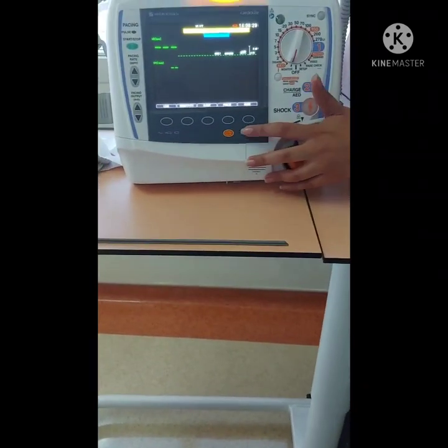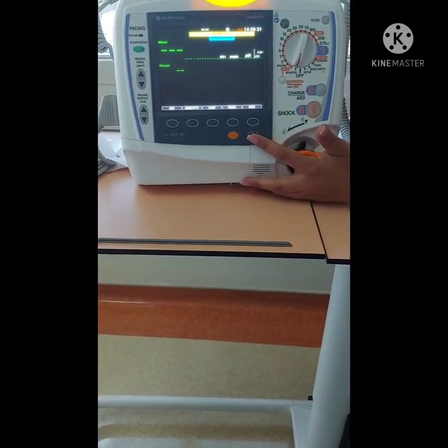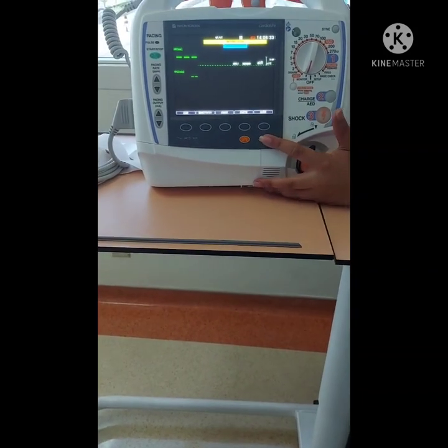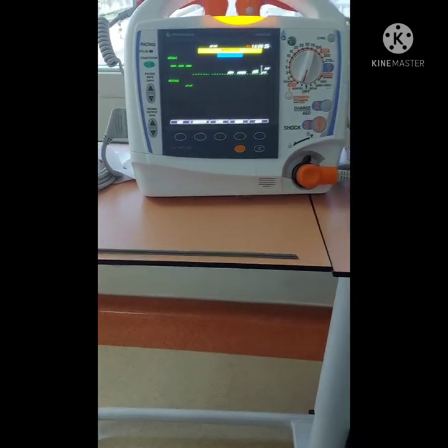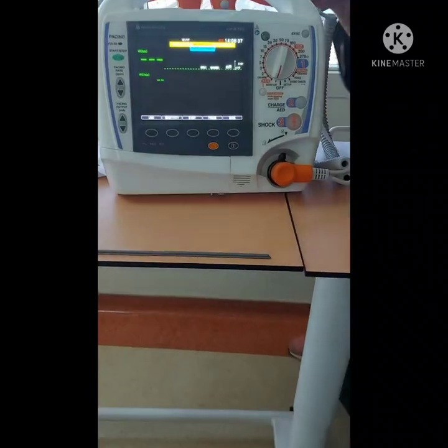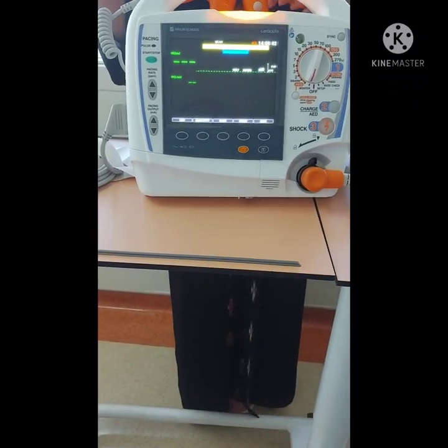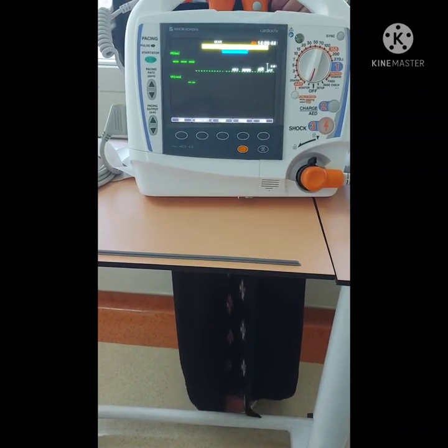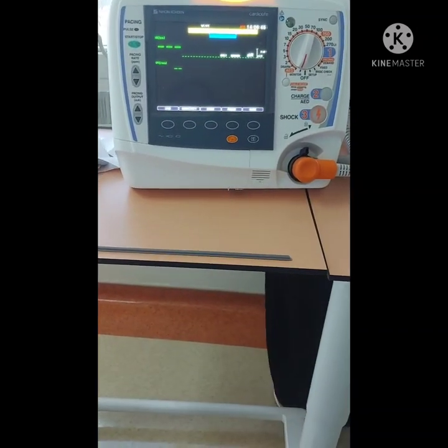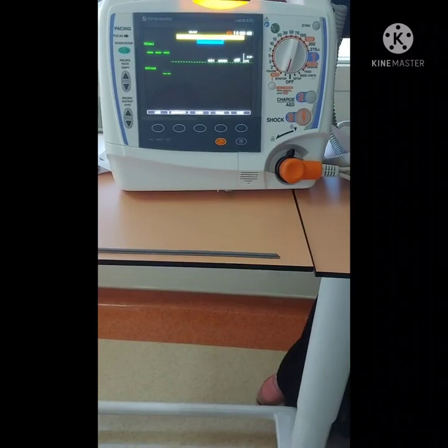And this one for the recorder. I press it and it's gonna print. It's not gonna stop until I press back. Okay. And if you do anything to the patient or you give a shock, it's gonna start printing until you finish the shock for the patient, then it's gonna turn back off.